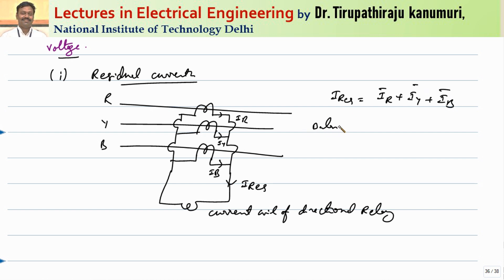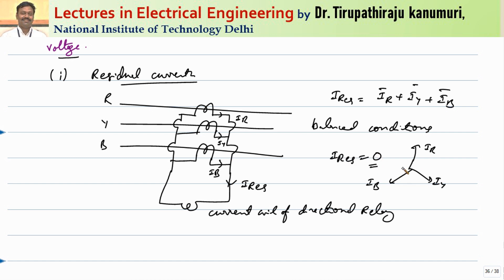Under balanced conditions, the values of IR, IY, and IB will have nearly the same magnitude. As they are displaced by 120 degrees, their sum will be equal to zero, so I-residual will be equal to zero. Even if there is a small unbalance, the residual current magnitude will be of lesser magnitude. We will make the current setting such that it will not operate for small values of unbalance, and we keep the setting according to the expected fault unbalance.